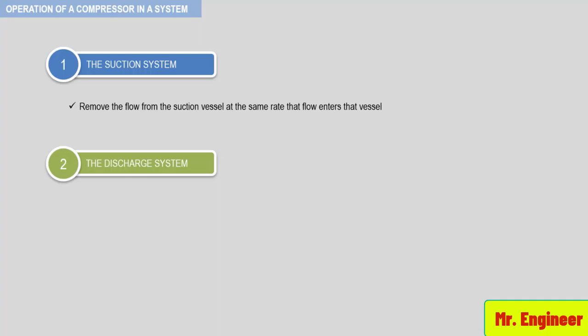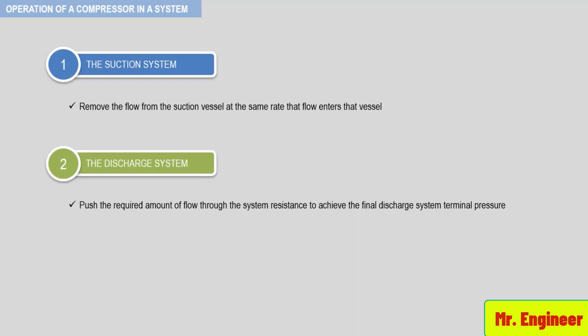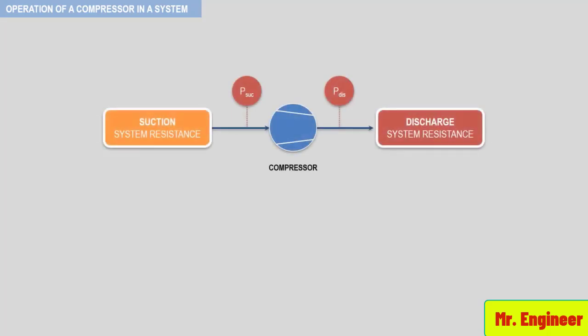In the discharge system, the objective is to push the required amount of flow through the system resistance to achieve the final discharge system terminal pressure. This pressure may be in a vessel, in a ship, or could be in a pipeline. The discharge pressure at the compressor flange is therefore the accumulation of the system resistance from the terminal or delivery point back to the compressor discharge flange. An important point to remember is that the compressor differential head, or energy required by the system, is the net effect of the discharge system resistance and suction system resistance.